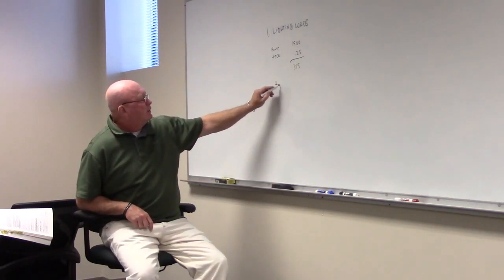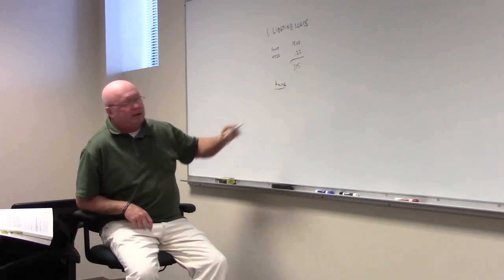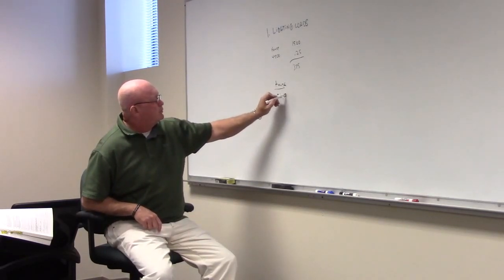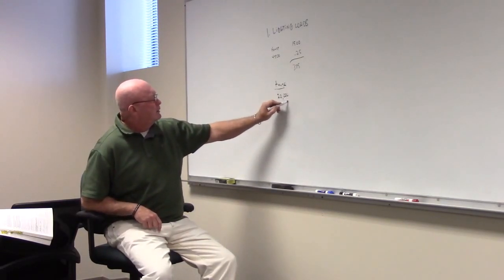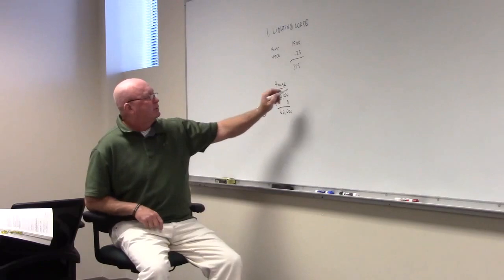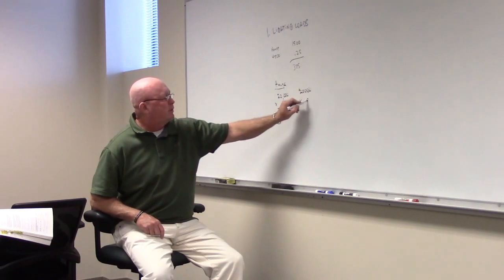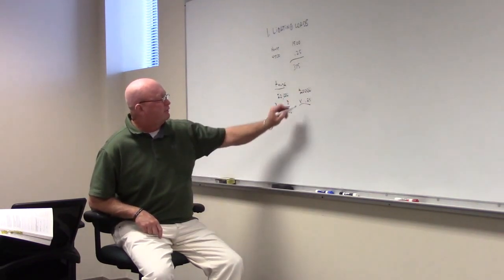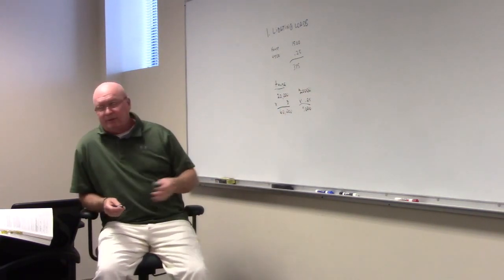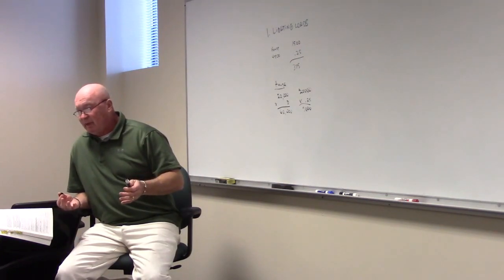But again, let's go back to last week where we were figuring lighting loads for James's house. It's 20,000 square feet times 3 is 60,000. We did the same thing with the warehouse. We did 20,000, that's a little bit more realistic. A 20,000 square foot warehouse. So then what is their load? Like 5,000? Is that what that is? So a considerable difference, because we're not going to light up a warehouse like we're going to light up our house, are we? Okay, and so that's step one.